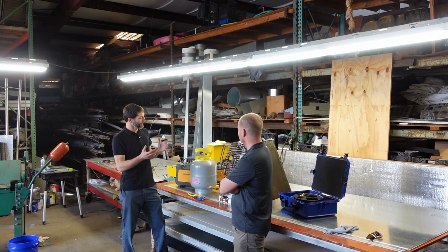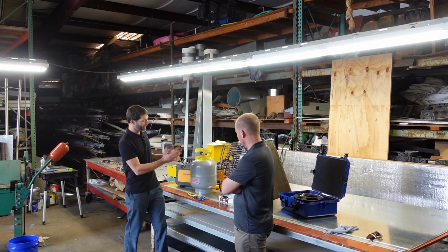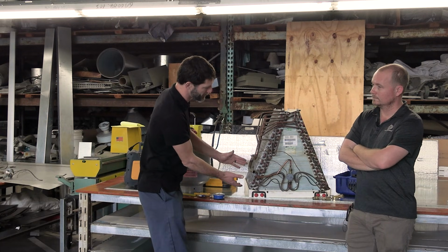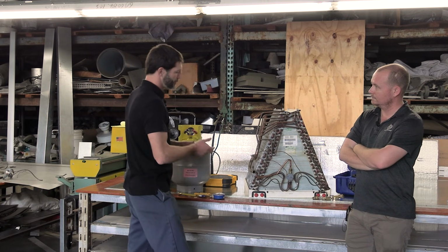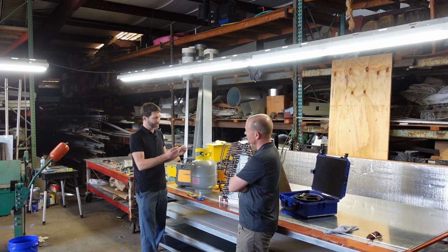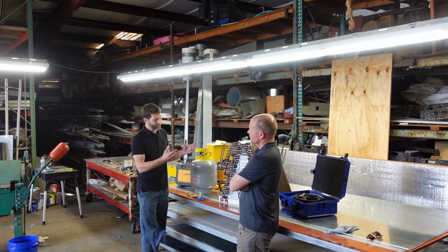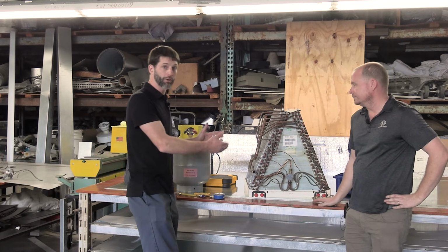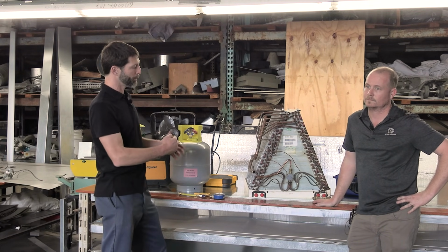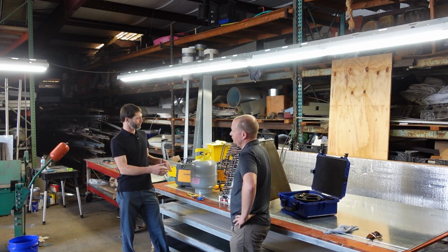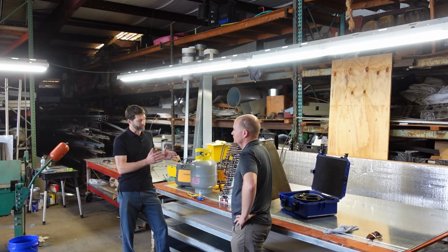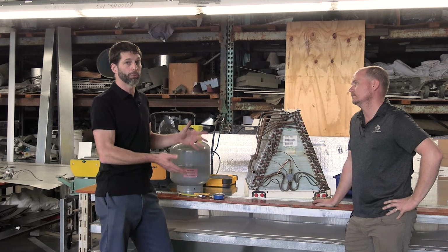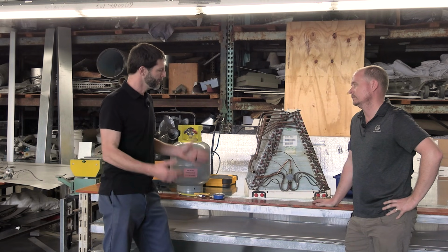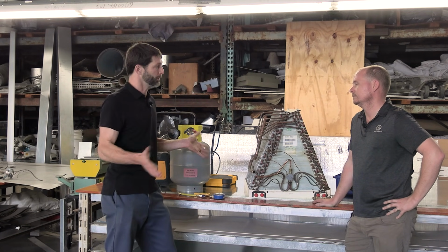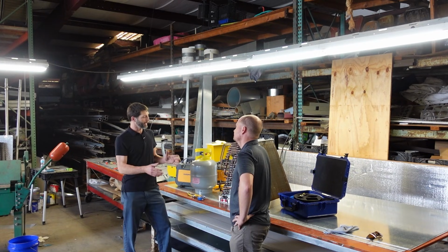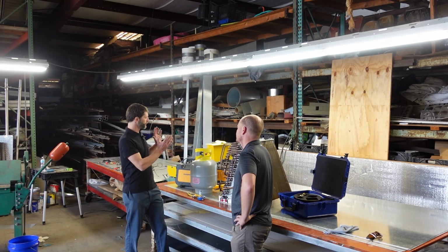Run the fan when you're recovering refrigerant, because when you're recovering refrigerant, you're lowering the pressure inside the system, and some of the liquid is not boiling off into a vapor unless you add heat to it. So you may think you're all the way down at 0 PSIG, and then you shut your recovery machine setup off, and all of a sudden the pressure rises. Well, why not just turn the indoor fan on during that time? It's something real easy to do, and you don't have to worry about turning your compressor on.